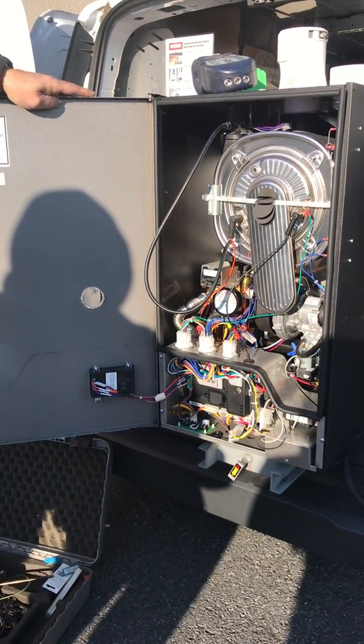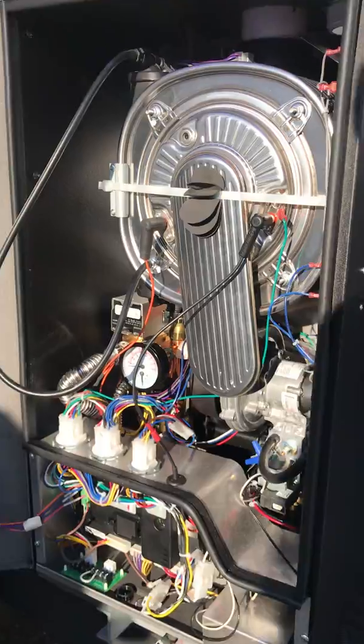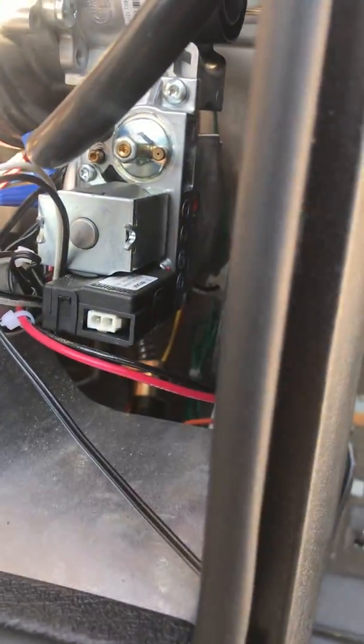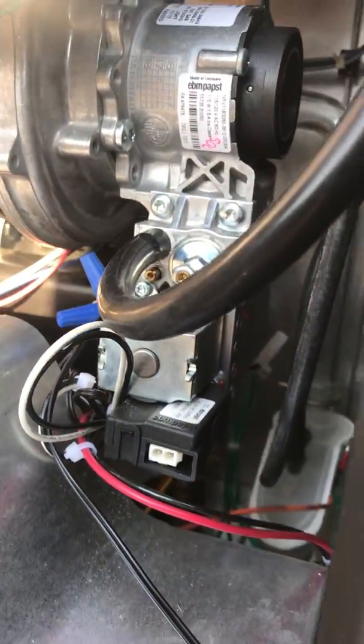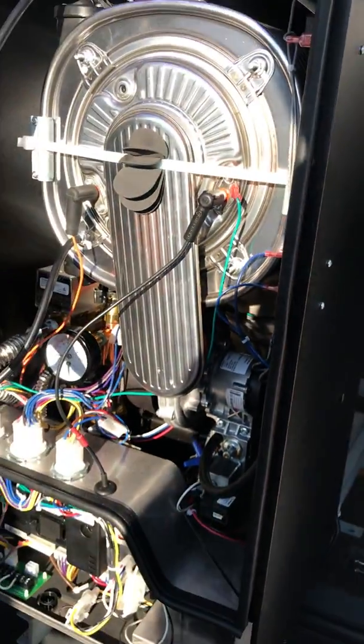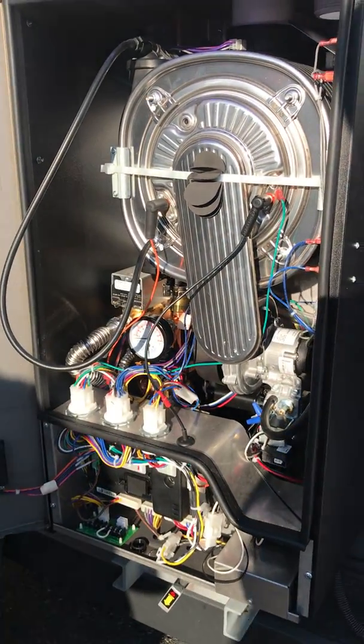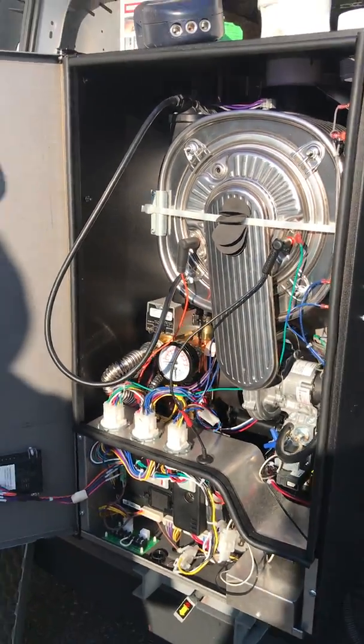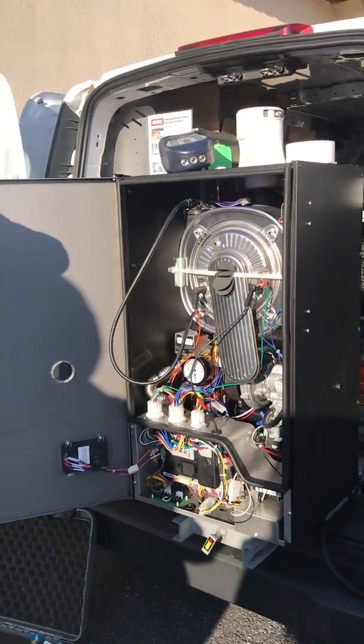That rectifier go bad? Rectifier can go bad. It's in the service kit. Now, you can actually check for your 24 volts AC. When the rectifier comes off, there's 2 wires and then there's a pole in the center. Those 2 pins, 24 volts negative. Negative, yeah. So now you can check and see whether that works.